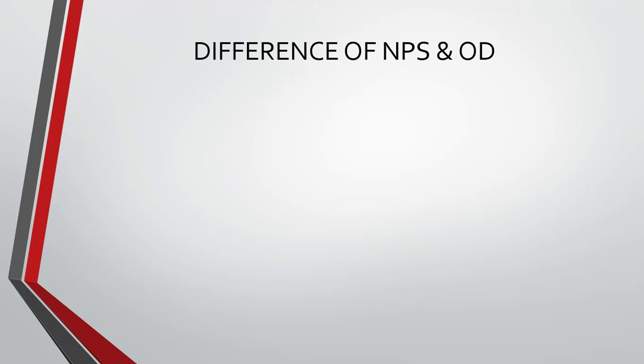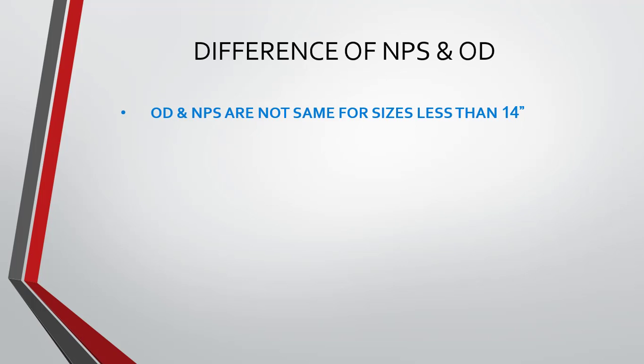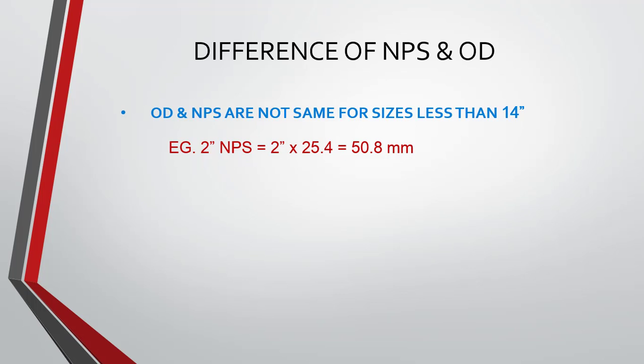Is there any difference between NPS and OD? Yes, there is a difference. For sizes less than 14 inches — starting from half inch up to 12 inch — OD and NPS are not the same. For example, a 2 inch pipe, if you convert to metric units, would be 50.8 mm. But the actual OD of a 2 inch pipe available in the market is 60.33 mm. That is why OD and NPS are not the same for sizes less than 14 inches.